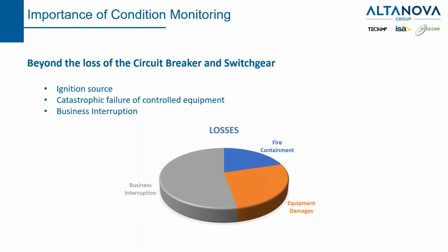We can summarize the losses beyond the loss of the circuit breaker and the switchgear with this graph, which shows, in very simple percentages, that the equipment damage is not the biggest part of the losses, and neither is the fire containment, that is actually to recover a disaster situation. But the most important losses, which can also worry the private supplier or the utility, are the business interruption.